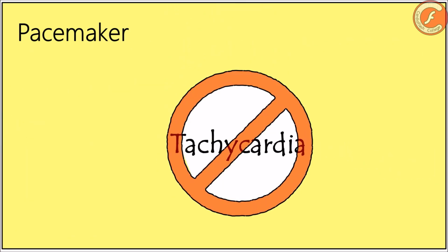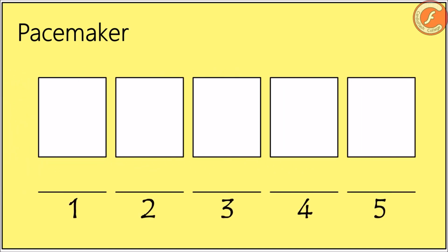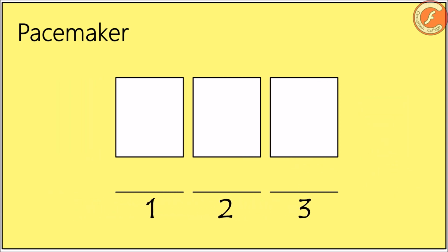And finally, it is important to point out that pacemakers can recognize tachycardias, but they are not designed to treat them. Another aspect that we must know about pacemakers is the international nomenclature used to designate the functions of cardiac stimulation. Although the complete nomenclature includes 5 characters, the most usual is to use the simplified version of 3 characters. In this way, the first letter indicates the stimulated chamber, being the options A in case of atrial stimulation, V in case of ventricular stimulation, and D in case of dual chamber stimulation.